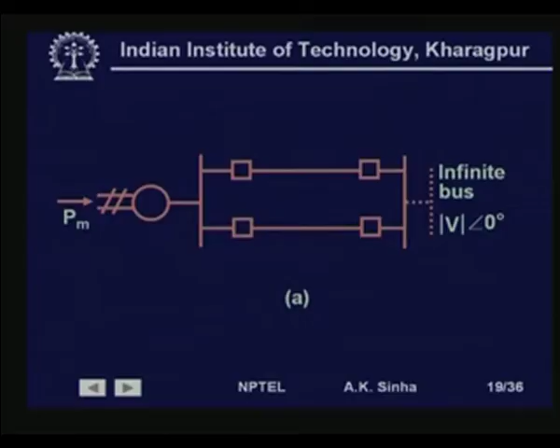So, this is what we have seen here. The electrical power output when one line is switched off, we write as Pe2 equal to E dash V divided by Xd dash plus X1 into sine delta, which we write as Pmax2 sine delta. When both lines are working, we have Pmax1 sine delta providing the electrical power angle characteristics for the machine with both lines on, and this is providing the electrical power angle characteristics when one of the lines is switched off, that is, when line 2 is switched off.